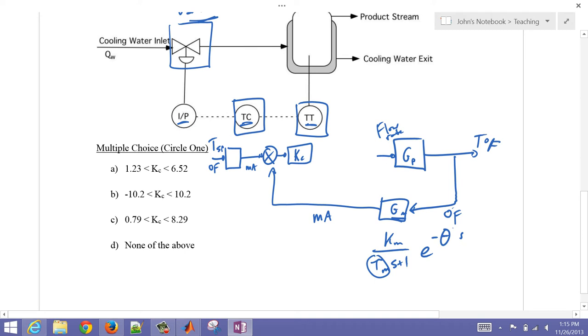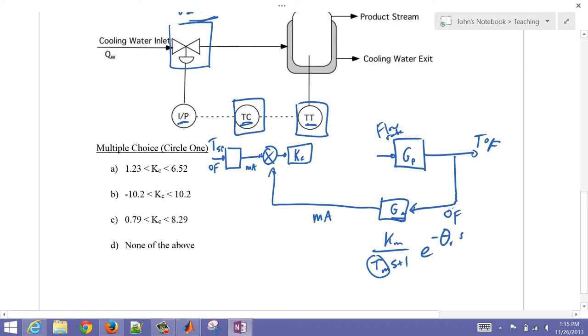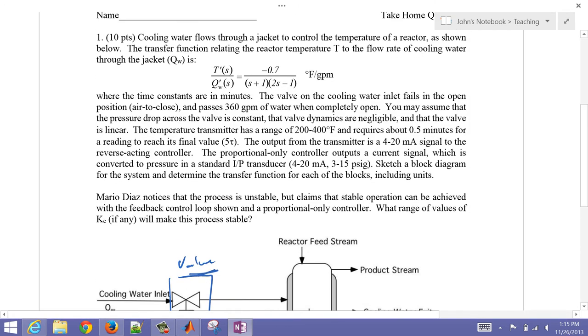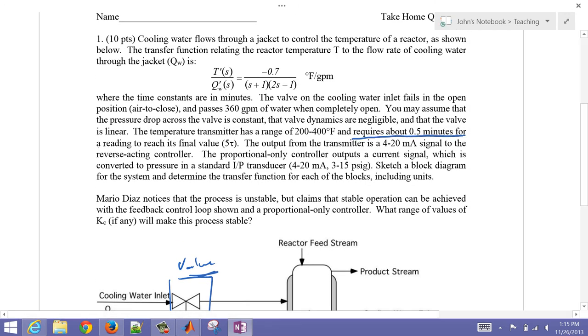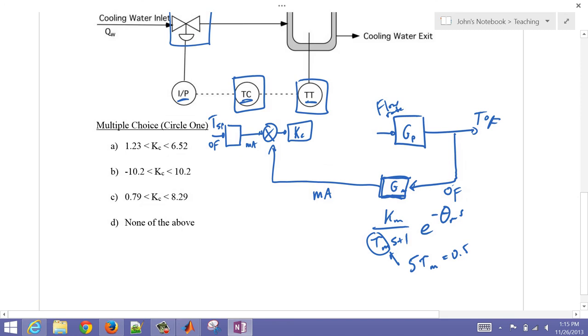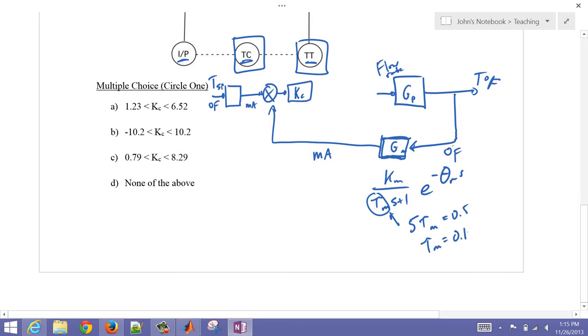In some cases, like a thermocouple — remember you did that for a furnace — you were trying to determine the time constant, to see if you could measure those fluctuations inside the furnace with the mass of the thermocouple. That's effectively what we're doing here: modeling the temperature transmitter dynamics. You have quite a large dynamic here — 5τm equals 0.5 minutes, meaning it requires about 0.5 minutes for a reading to reach its final value. So τm equals 0.1 minutes.